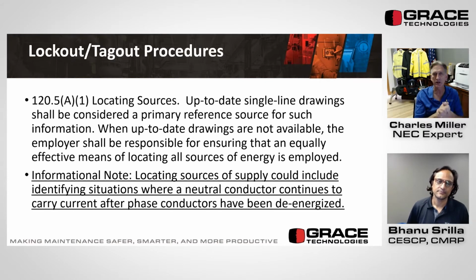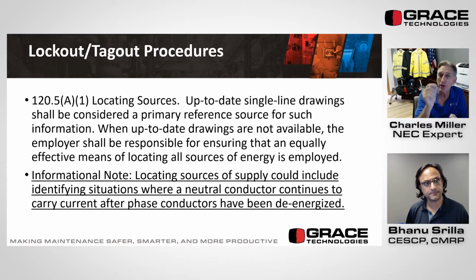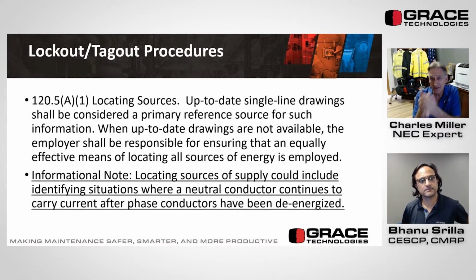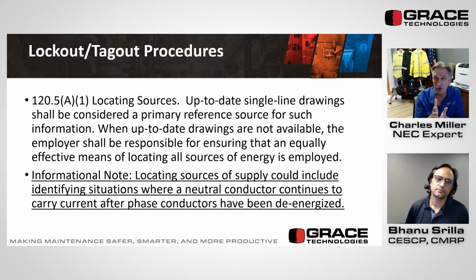And the informational note just gives a little insight. If there's a neutral, and it's part of a multi-wire circuit, it's not going to be a problem if that neutral is connected to a 3-pole breaker and you turn the 3-pole breaker off. If that's all that neutral wire is feeding, then that circuit will be off as well. And that's why when we're testing for the absence of voltage, we test phase to phase and phase to ground. Well, if it's a neutral, like we've got 3 hots and a neutral and a ground, then we're going to have to throw our testing of the neutral in there as well.